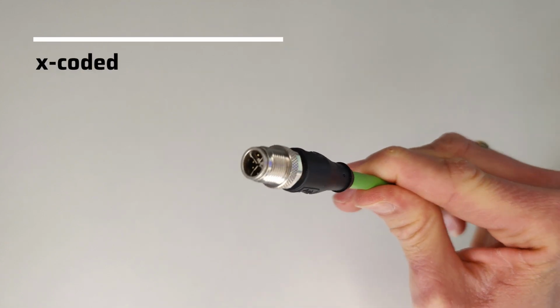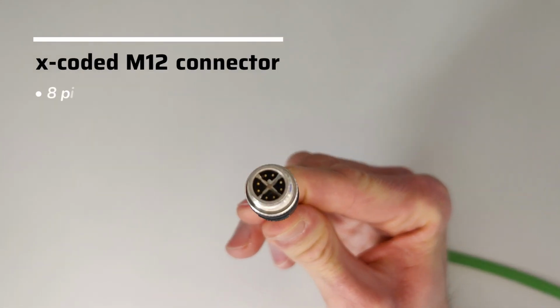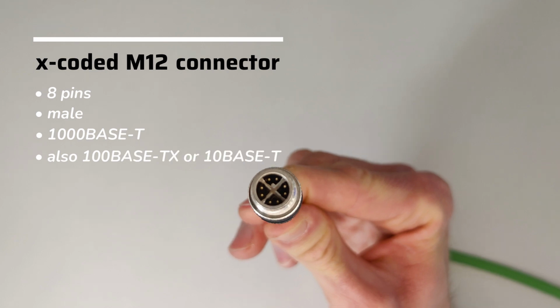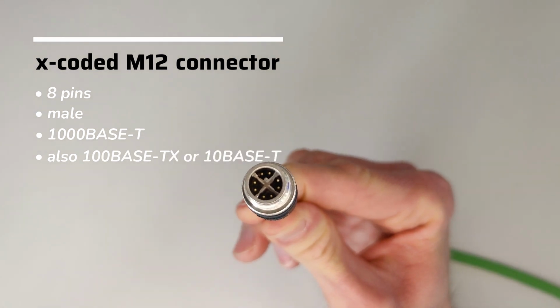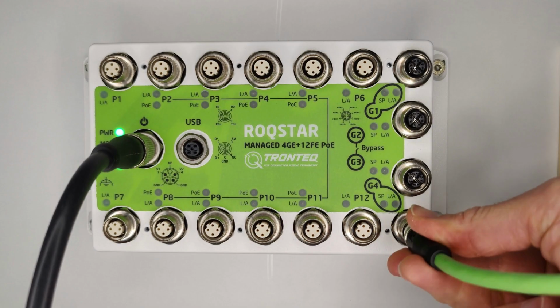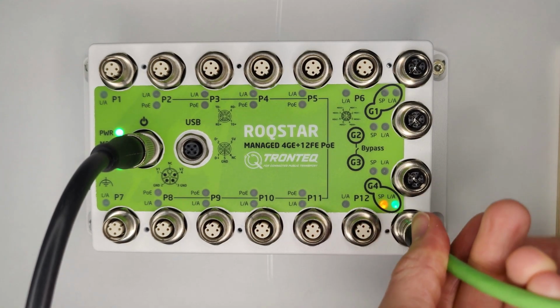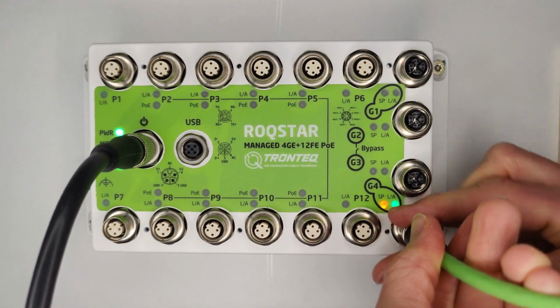The other type is an X-coded M12 connector with 8 pins, also male at cable side. 8 pins are needed for gigabit Ethernet, so you can establish links with up to 1000 megabits per second. Ports with this gigabit connector are also capable of establishing links with 100 megabits per second and 10 megabits per second.